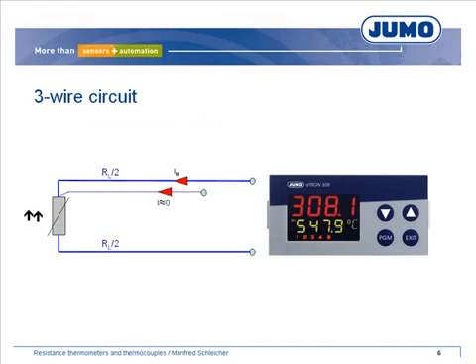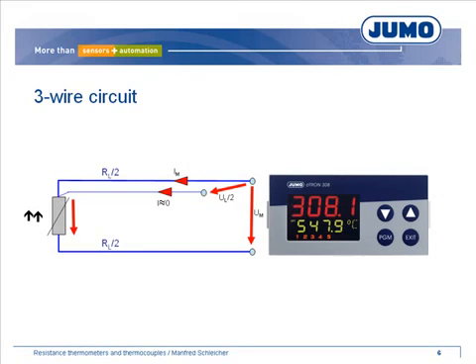In the event of a three-wire circuit, the voltage drop on one wire is measured. Due to the high internal resistance of the device, the current on the third wire is practically zero. The device subtracts twice half UL from the measured voltage, so the voltage drop of the resistance thermometer and the real resistance value can be calculated. The three-wire circuit is the most often used circuit version in the industrial sector.